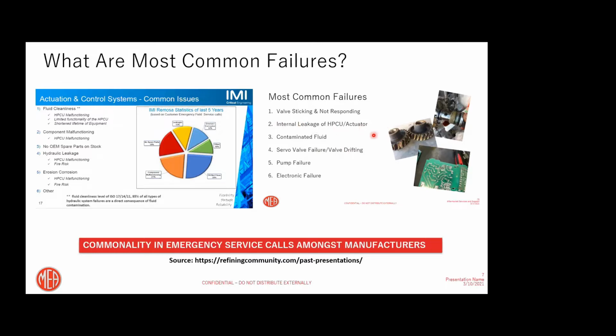Additionally, you always have internal leakage over time. There is a lot of tubing and a lot of high pressure hosing around, which runs back and forth. So if the seals deteriorate or fittings get loose, you get a leak. Additionally, you of course get pump failures and electronic failures. These are basically common things, and we all have basically the same problems with these hydraulic power control units.